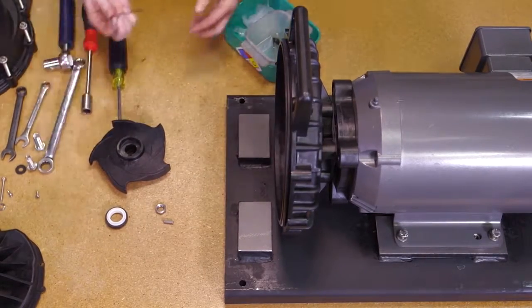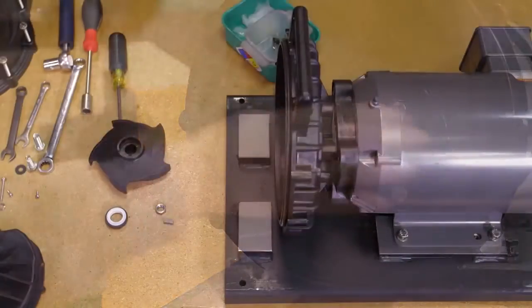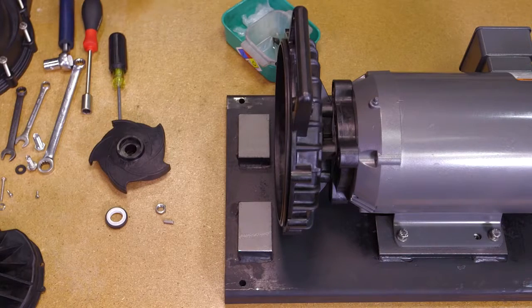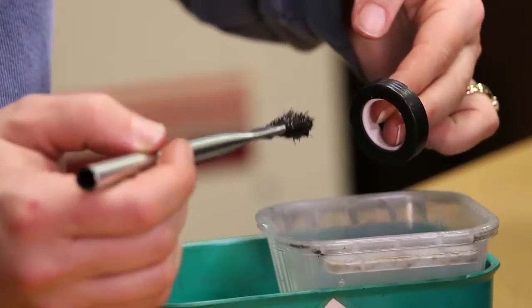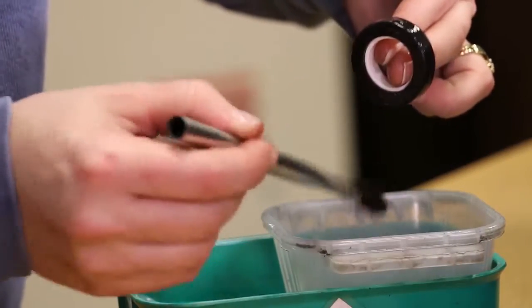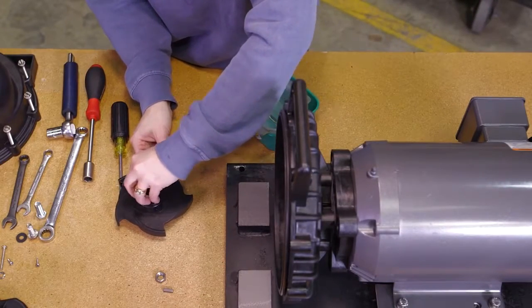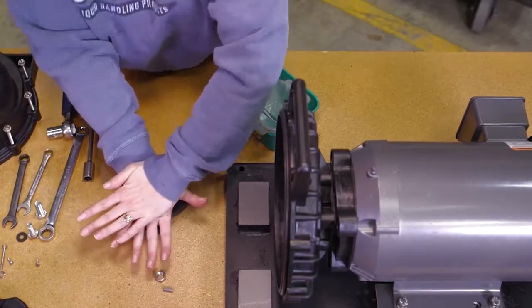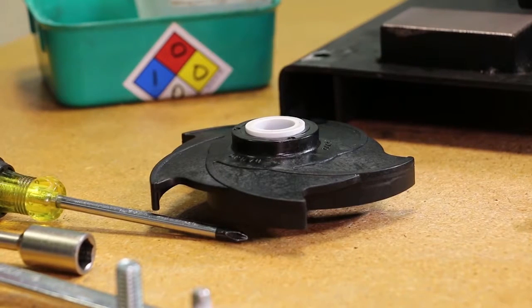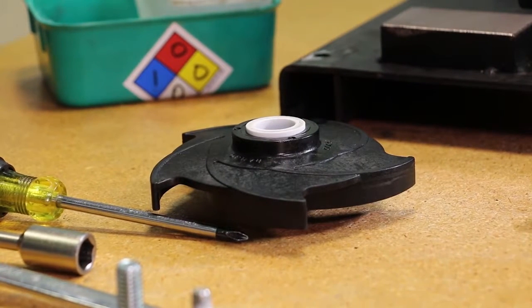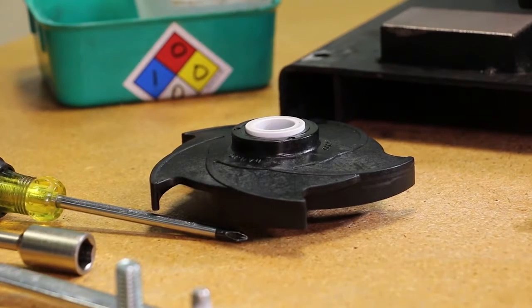Install the O-ring segment onto rear bracket after lubricating with petroleum jelly. Install the ceramic seal half into the impeller. Be careful when handling the seal to not scratch the seal surface. The outside diameter of the rubber boot may be sparingly coated with silicone to ease installation. The seal half is pressed into the hub of the impeller by hand, but make sure to press uniformly. It's important to be absolutely sure that the ceramic seal half is bottomed out and installed squarely. If the installation is not square, seal wobble will occur, leading to premature seal failure.